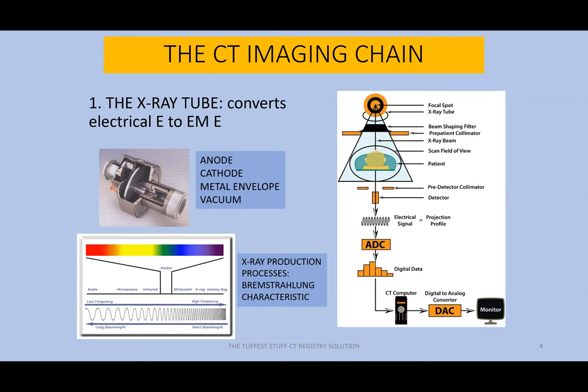If it happens to a great degree, we call it a gassy tube. Test answer: a gassy tube is when there is a lot of gas liberated from the metals because of the heat in the X-ray production process. In the X-ray production process, remember there are two: Bremsstrahlung or braking radiation, and then characteristic radiation.